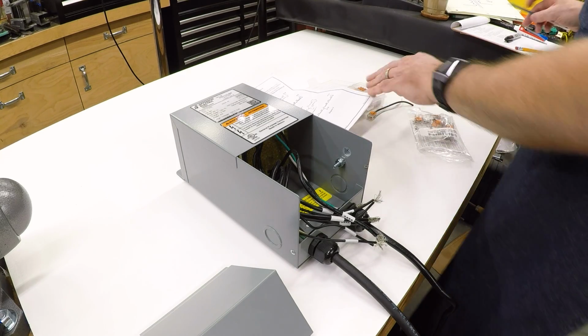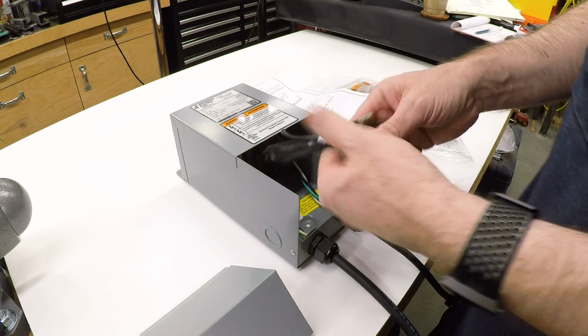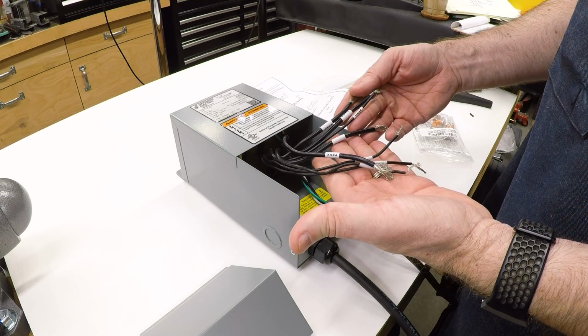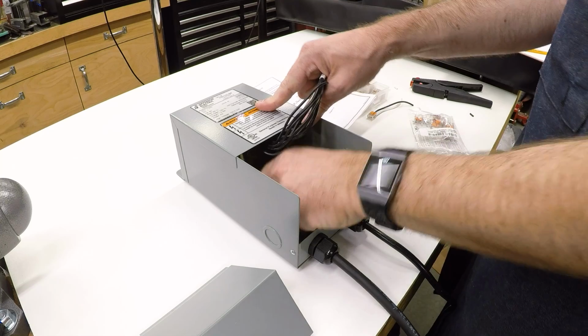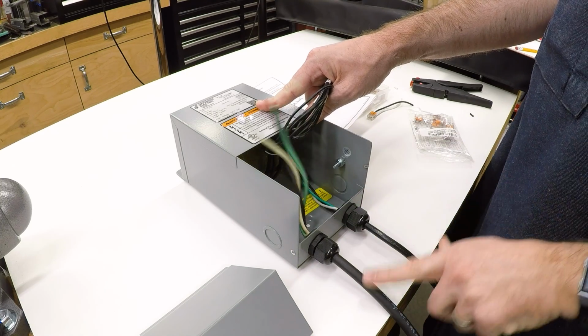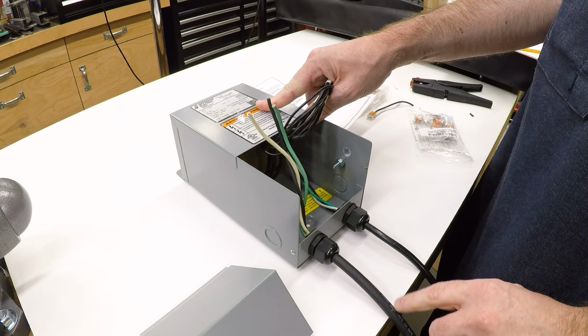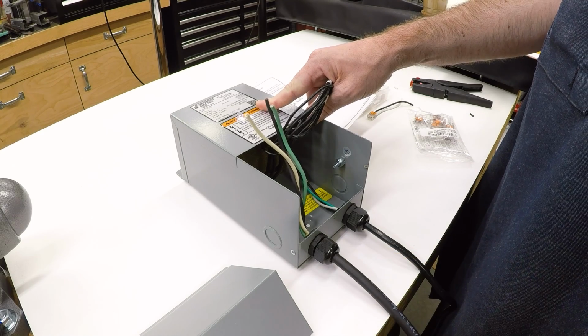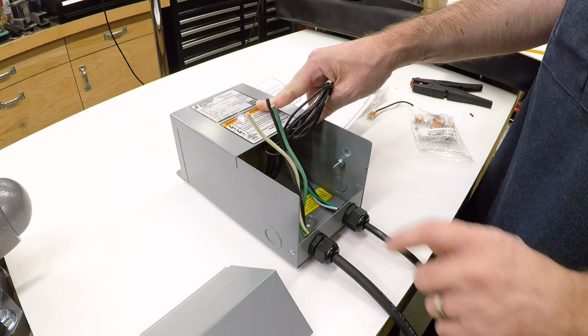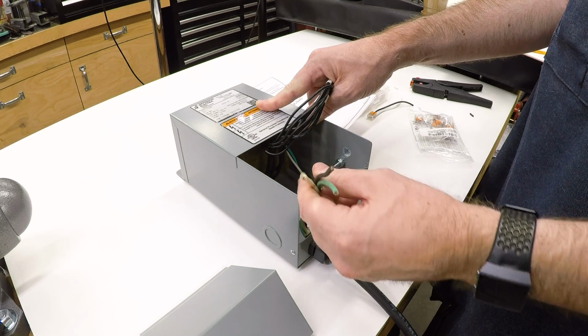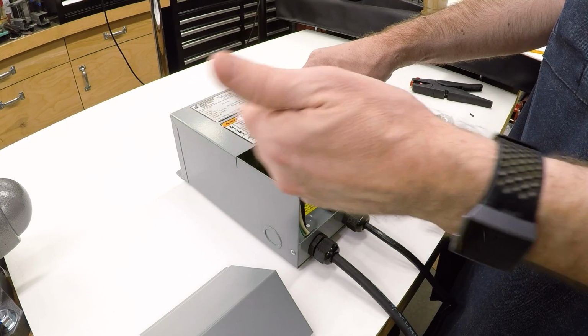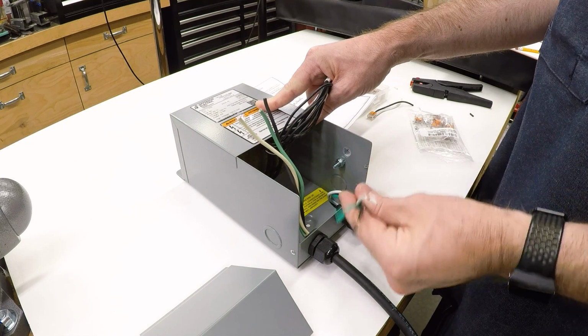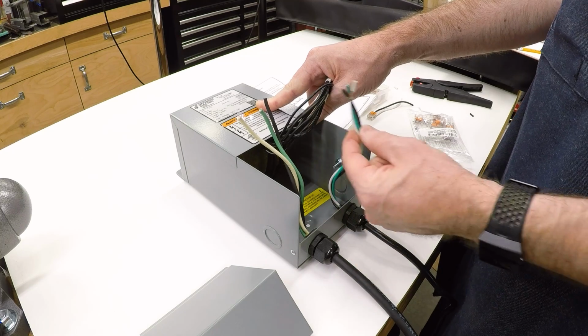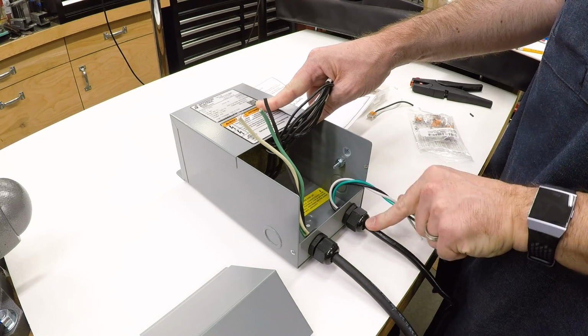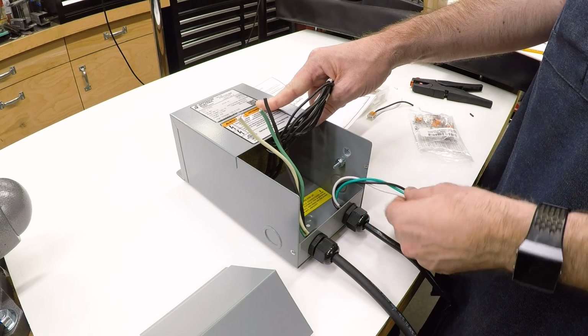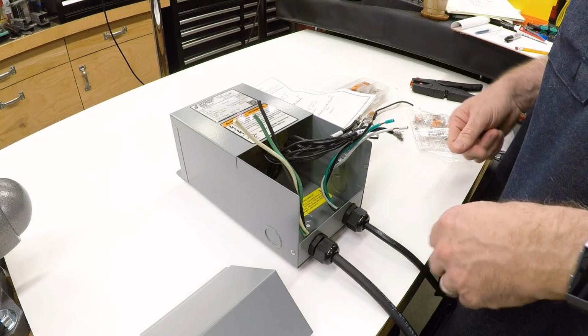So I've got my wiring diagram here, and I'm going to start connecting things together. I've got all the wires from the transformer, and they're all labeled. Then I've got my input - I've run my input cable, which is SJOOW, Service Junior oil-resistant cable, 12-3, meaning 12 gauge conductors: ground and the two legs of the AC. The output is a slightly smaller gauge, but that's just the cable I cut off the tool itself, so that's my output on the low voltage side. I'll make all of these connections.